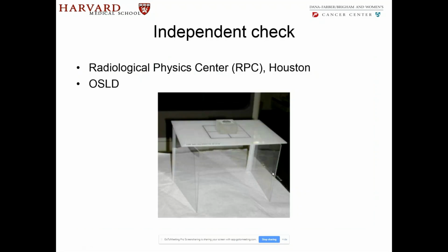Once you are done with all this, it's good to have a second independent check on your calibration. For that, we seek help from the Radiological Physics Center, RPC, in Houston. They send us a set of OSLDs, the phantom, the entire system. We provide them the irradiated OSLDs from our machine. The procedure is also described by them, and within 2 weeks we get the result from them. If it is within 1%, we are very happy. If it is not within 1%, then we have to go back to the machine and adjust it accordingly.